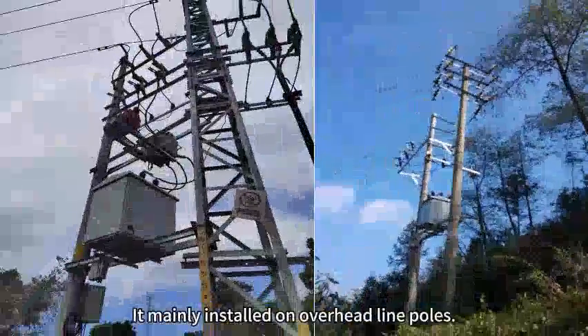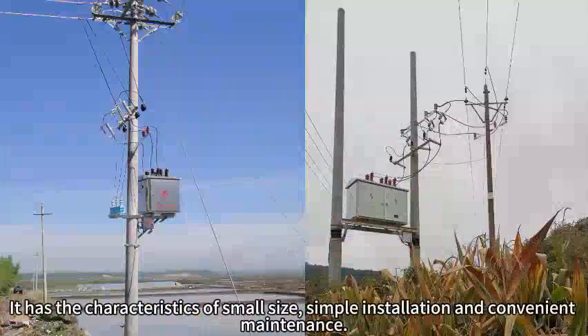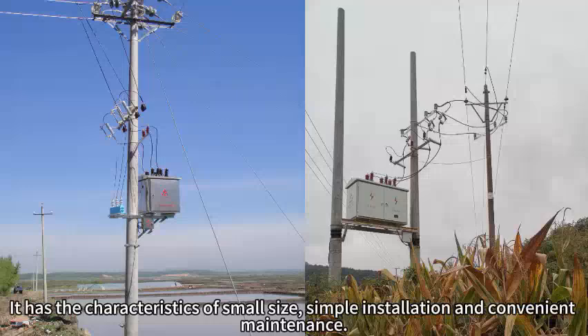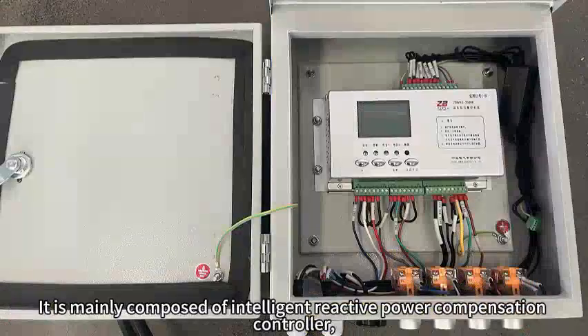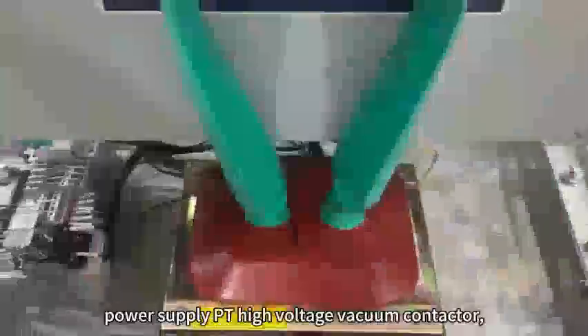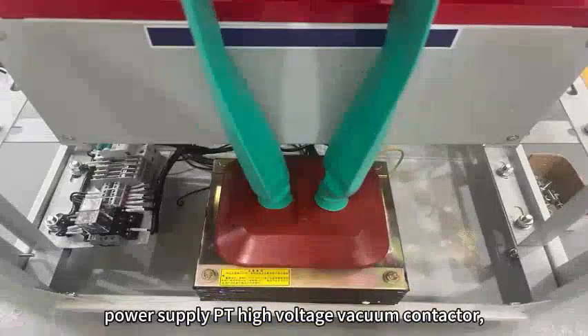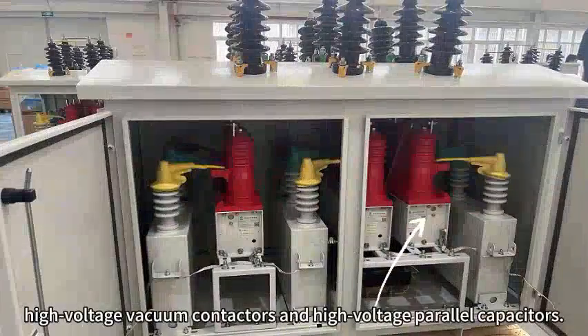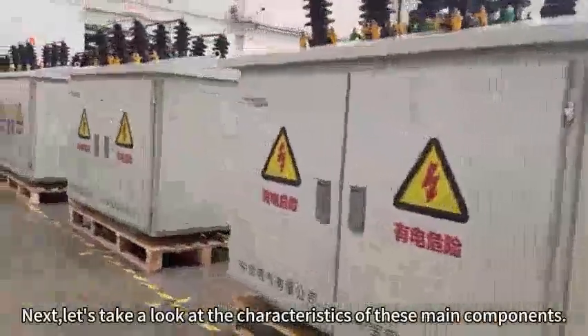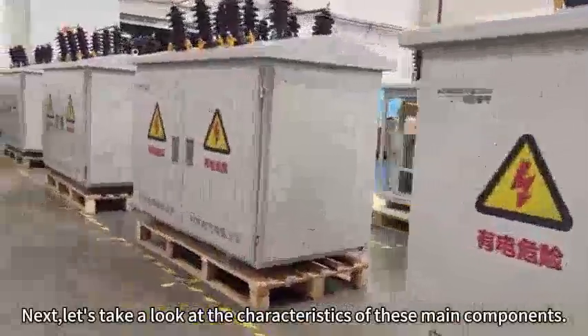It is mainly installed on overhead line poles. It has the characteristics of small size, simple installation, and convenient maintenance. It is mainly composed of an intelligent reactive power compensation controller, a current sampling sensor, a power supply PT, a high voltage vacuum contactor, and high voltage parallel capacitors. Next, let's take a look at the characteristics of these main components.